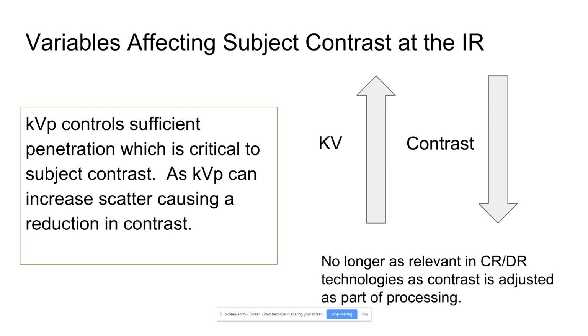The rationale is a couple of things. Like we said, digital imaging systems work better with higher exposure, and higher kV leads to higher exposure. And also you ensure that you're penetrating the part. And third, you can lower the dose if you have an associated reduction in mAs. So if the kV goes up and you lower the dose significantly by lowering your mAs. If they both go up, then you're not lowering any exposure, right?